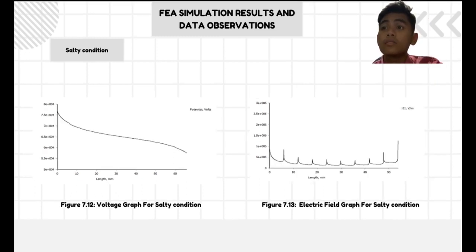Okay, for the salty conditions, based on figure 7.12, the voltage graph in salty condition shows that when an alternate shed 132 kV insulator is exposed to salty condition, the presence of salt deposit can have a significant impact on its electrical performance. The voltage graph in such condition typically shows an increase in initial voltage and a decrease in insulation resistance over time, or over 60 mm length.